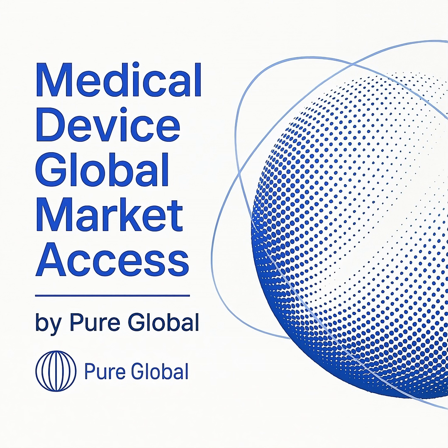However, if a Class 1 device is sterile, has a measuring function, or is a reusable surgical instrument, it requires notified body involvement. A notified body is an independent organization designated by an EU country to assess the conformity of certain products before being placed on the market.